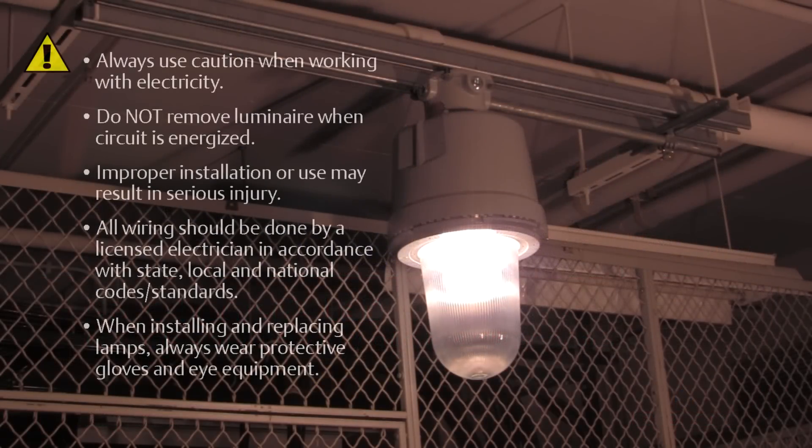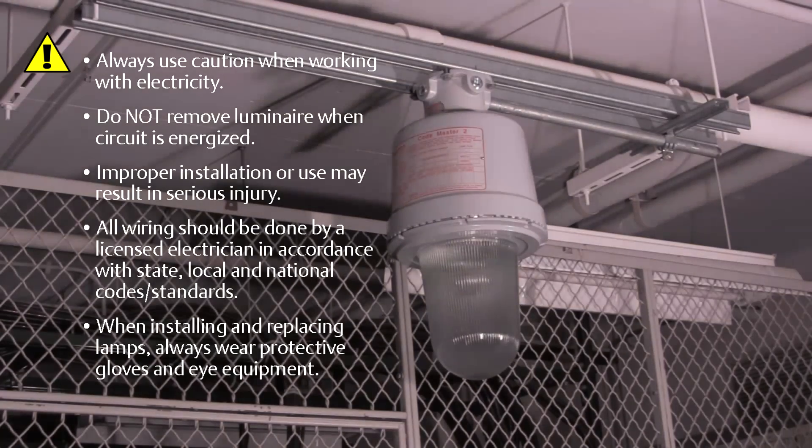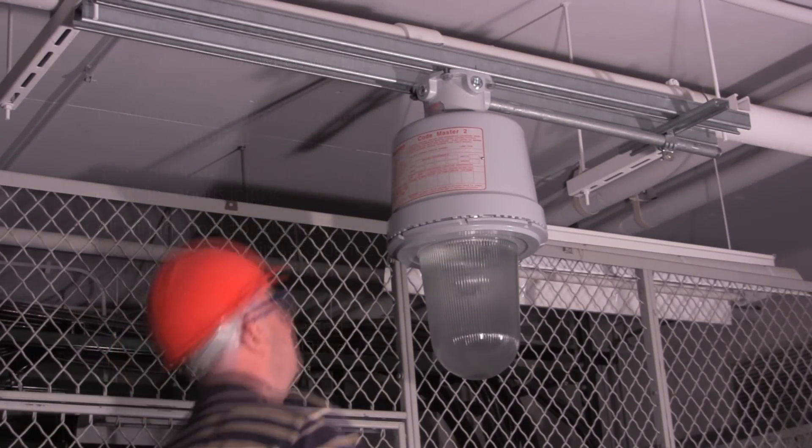Today we are going to show you how easy it is to replace an existing explosion-proof Appleton Codemaster HID lighting fixture with a new Codemaster LED fixture. First, you want to make sure that you turn off the power to the existing Class 1 Division 1 fixture.